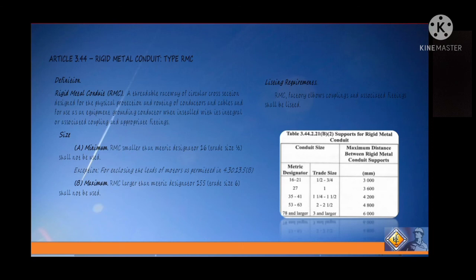Next in 3.44, which is the rigid metal conduit or the type RMC. For the definition, RMC is a threadable raceway of circular cross-section designed for the physical protection and routing of conductors and cable and for use as an equipment grounding conductor when installed with an integral or associated coupling and appropriate fittings. So for the size of our type RMC, for the minimum, RMC smaller than metric designator 16, trade size of 1/2, shall not be used.